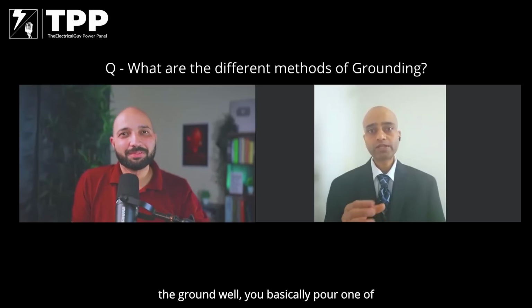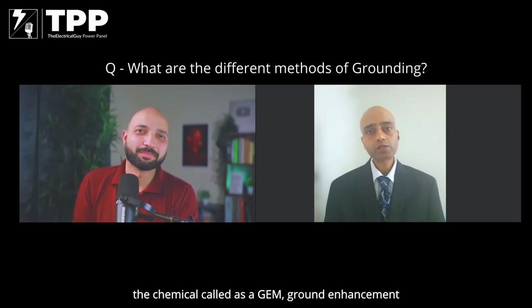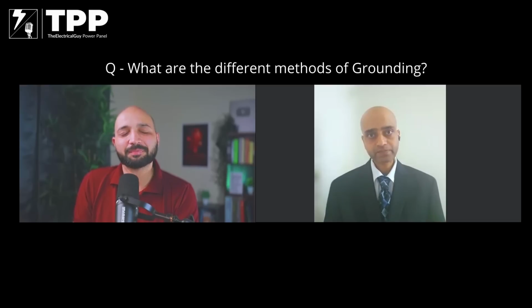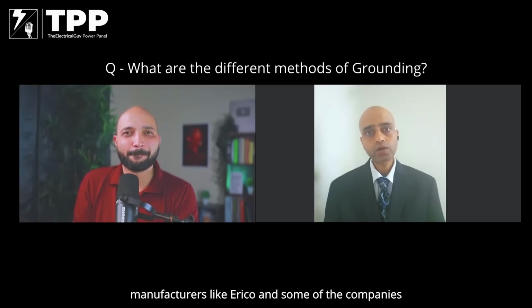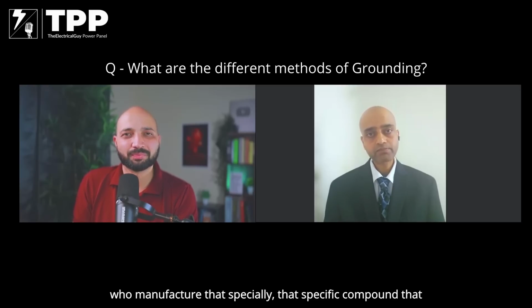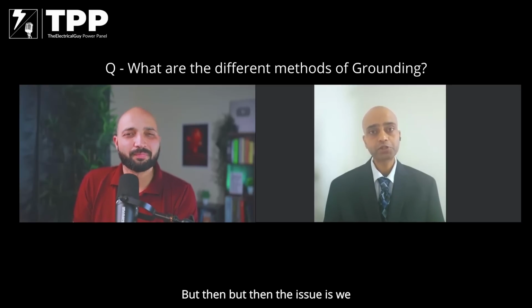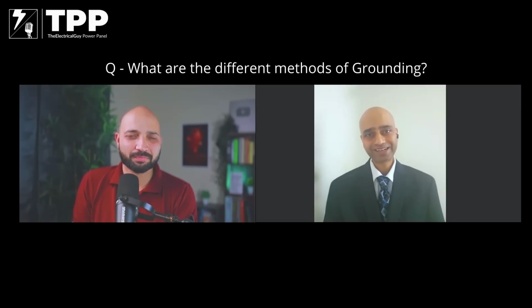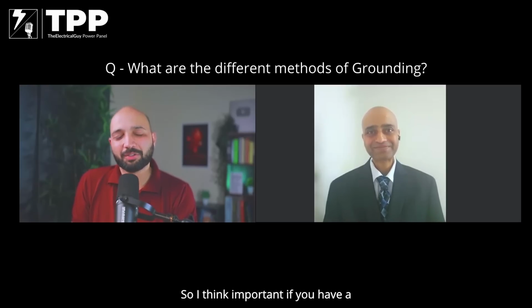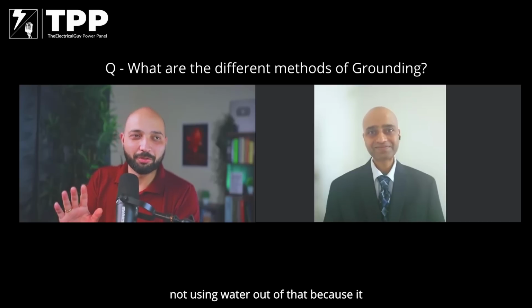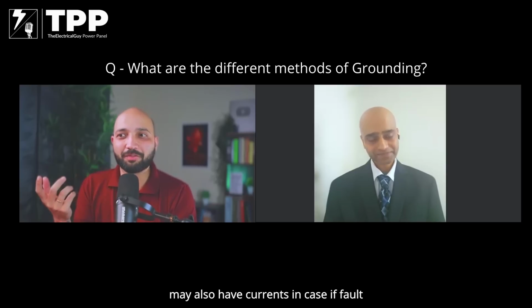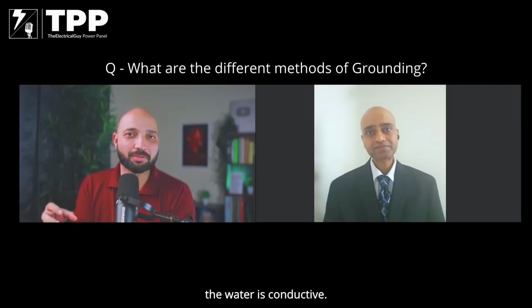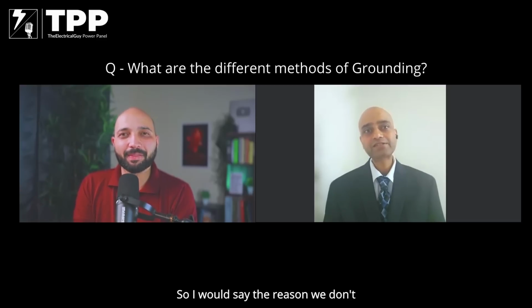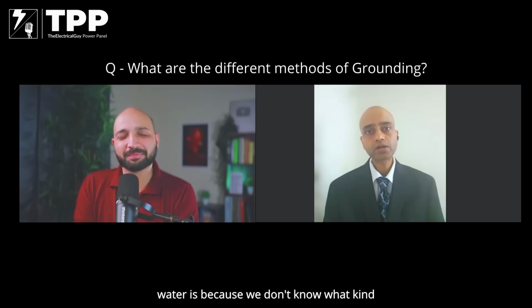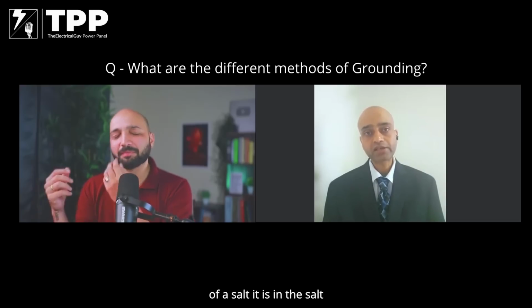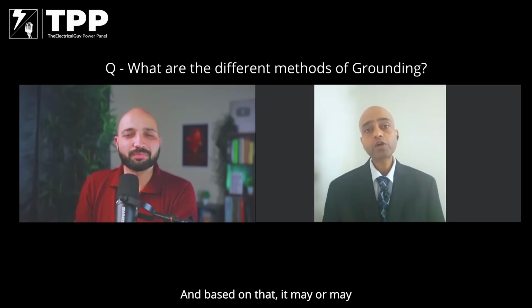So what happens is when you dig the ground well, you pour a chemical called GEM, ground enhancement material. That's a combination made by manufacturers like Erico and some other companies who manufacture a specific compound that retains moisture. But we do not want the whole well filled with water. So if you have a well near the substation, make sure you are not using water from it, because it may also have currents. In case a ground fault is happening, the water may be conductive. The reason we don't want our well filled with water is because we don't know what kind of salt composition is in the water, and based on that, it may or may not corrode our electrode.